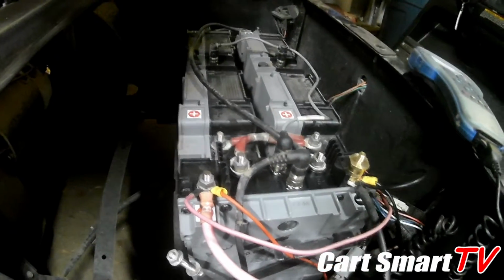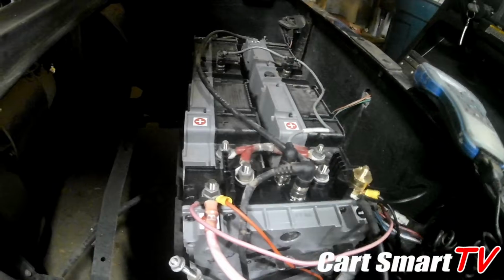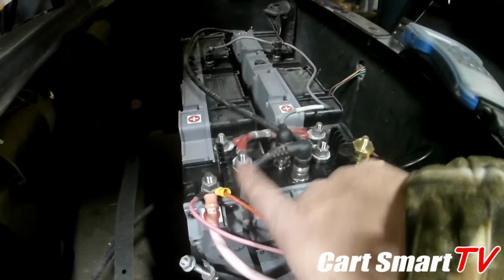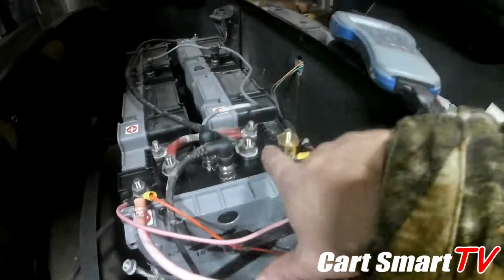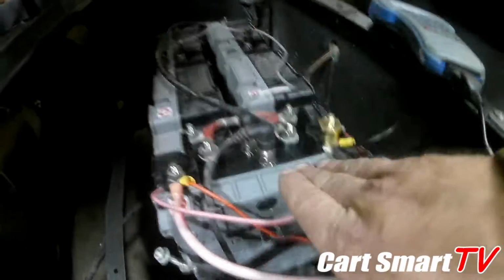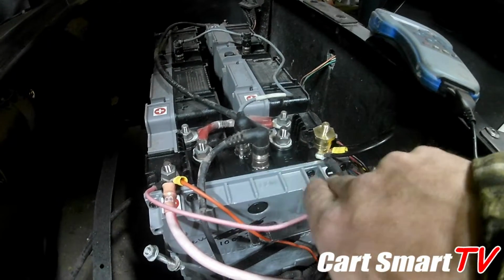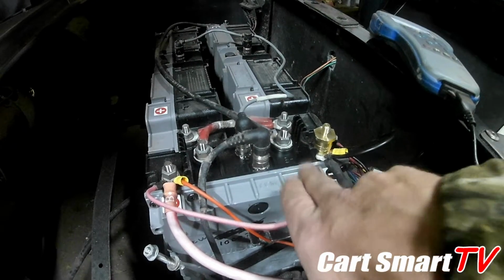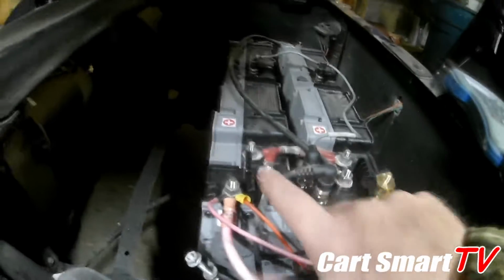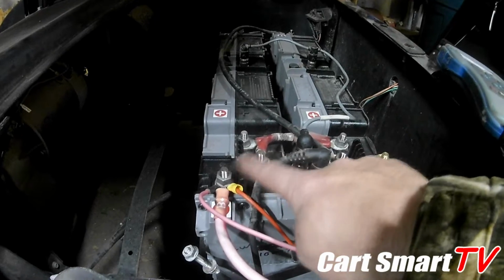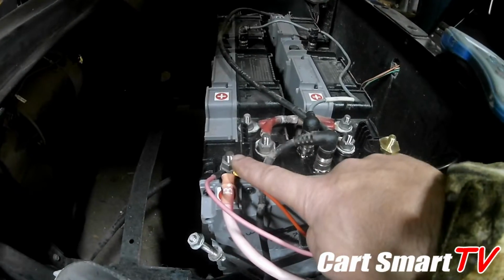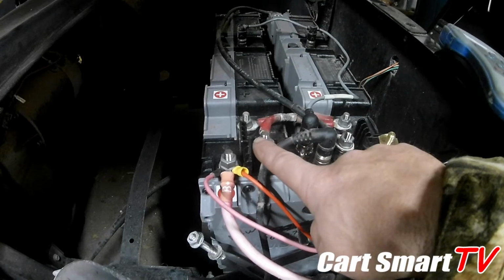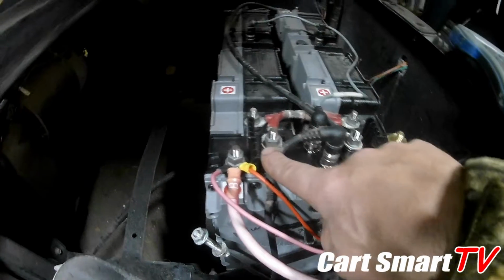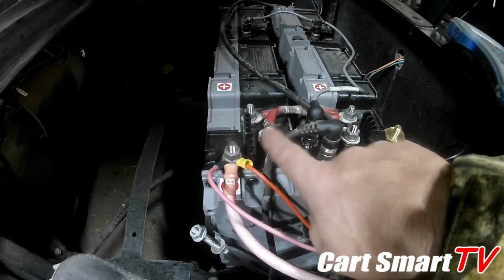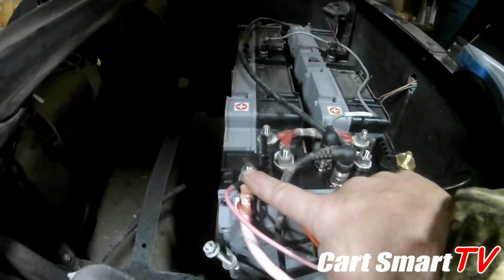Now that we've got a little bit of info on these two being bus barred together, and these two being bus barred together, or some type of busing system here underneath where we can't see - it came to be that this side right here, the bus connecting these two in the module, failed, and they were no longer busing together. So it was never going to show me power out here like it did in here.